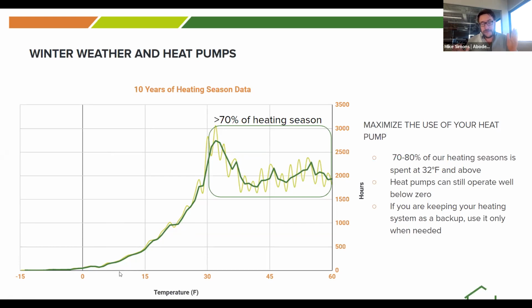So say, for example, a 3-ton heat pump — if it's negative 15 degrees outside, instead of being a 3-ton heat pump, it's probably more like a 2.5-ton heat pump. You might ask, if I needed 3 tons but only have 2.5 tons at negative 15 degrees, what happens? The answer is nothing catastrophic. The heat pump is still introducing 2.5 tons worth of energy into your home. So instead of keeping it at 70 degrees, maybe it only heats to 64 or 63 degrees.